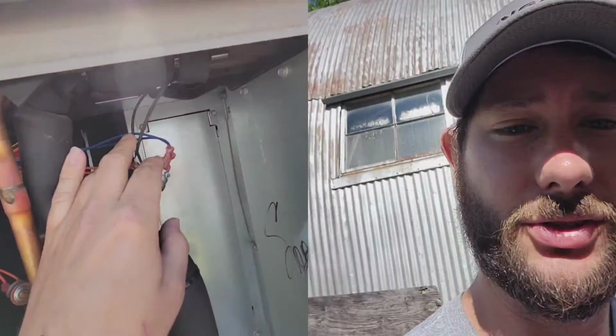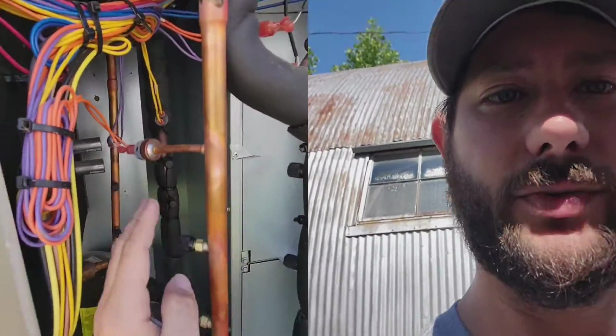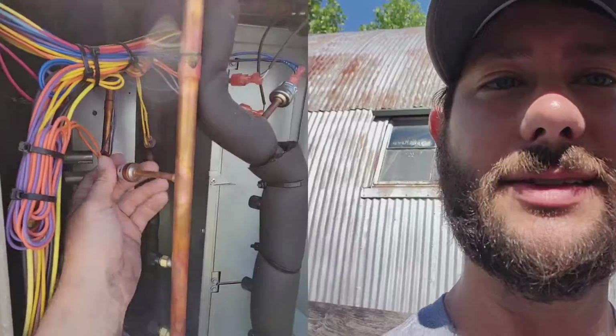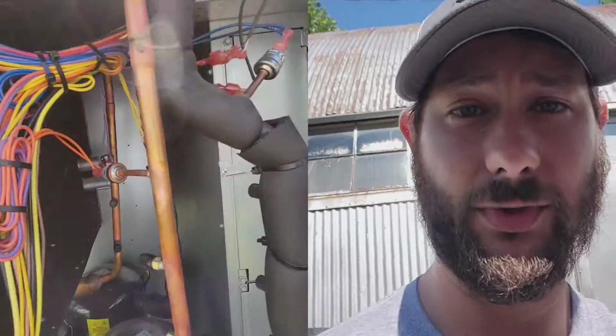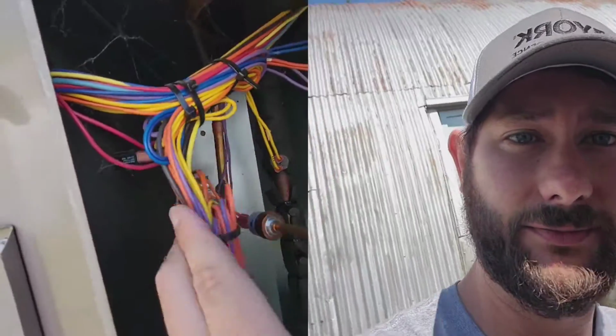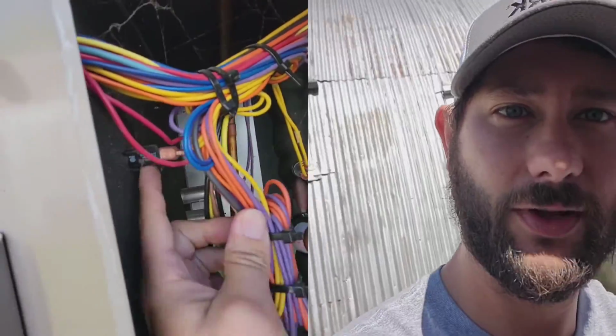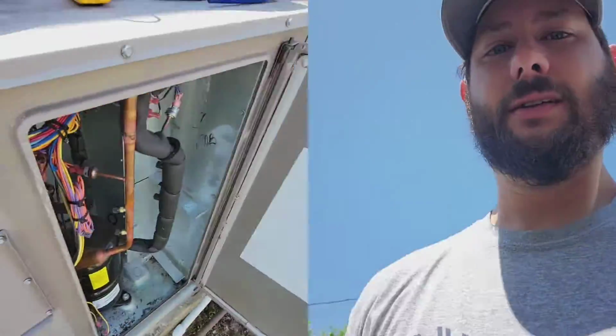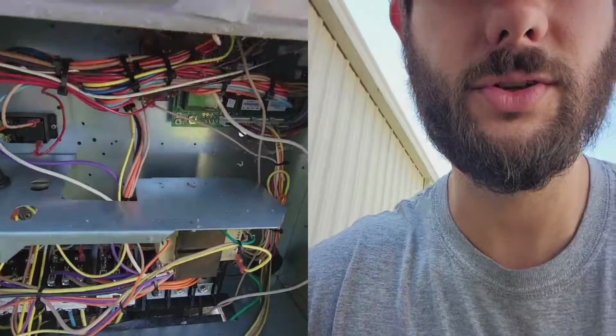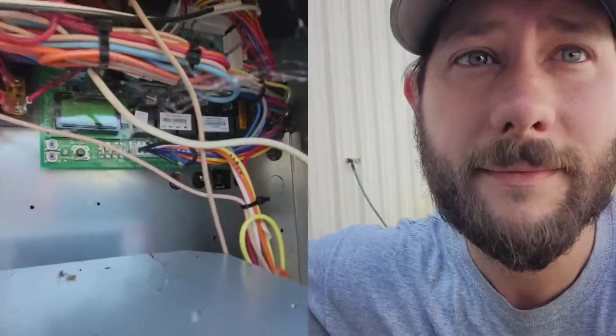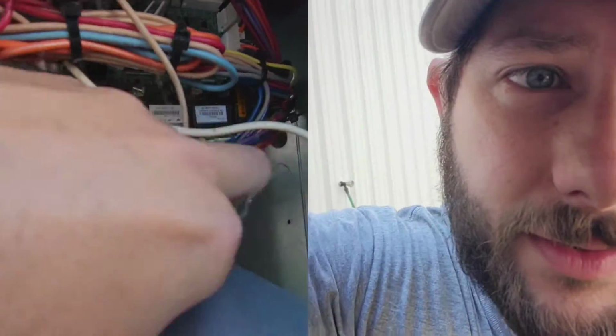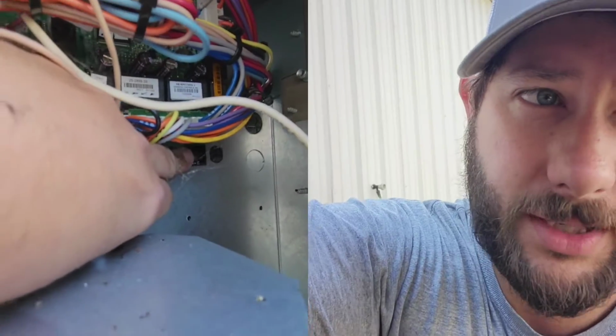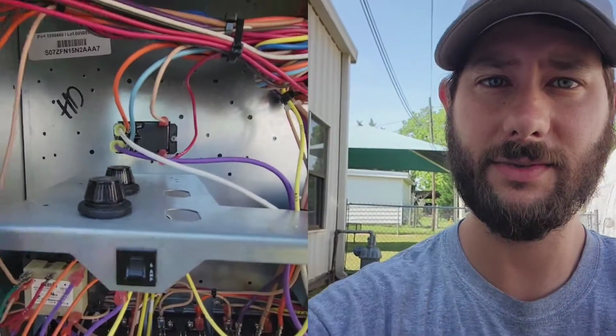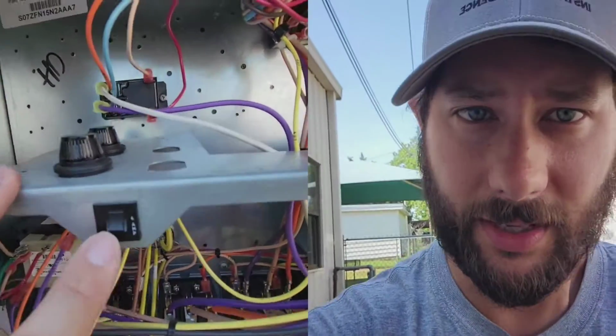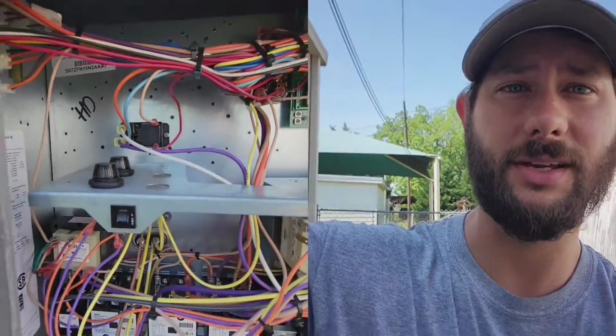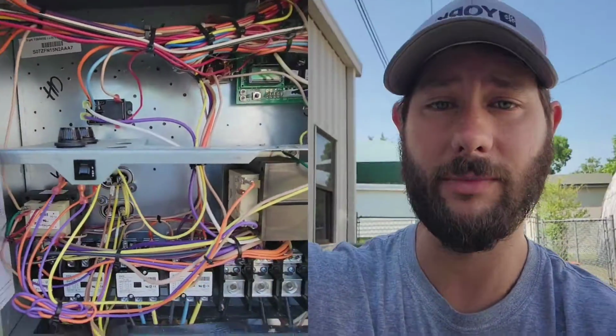This right here is your pressure switches. This one's for your discharge. This is your high side pressure switch, low side pressure switch. Those are 24 volts. And then you can see, oh, I've got some 24 volt resettable fuses here. So you need to check those when you go to a new job. See right there, there's a resettable fuse. And then this right here is a couple fuses. And then that's another resettable. These are things you need to check when you go to work on equipment like this.